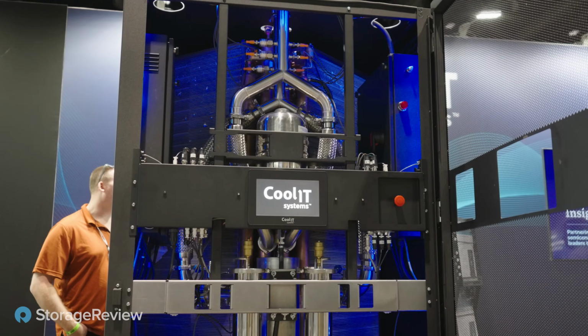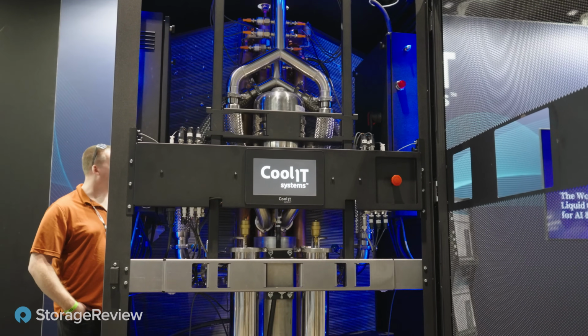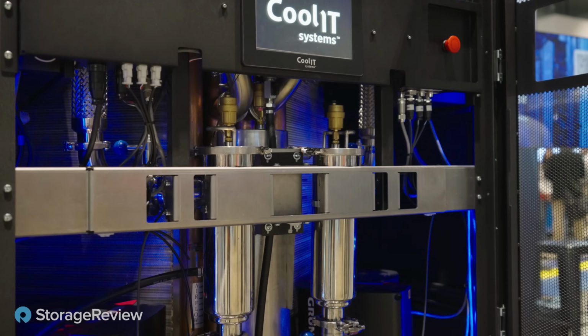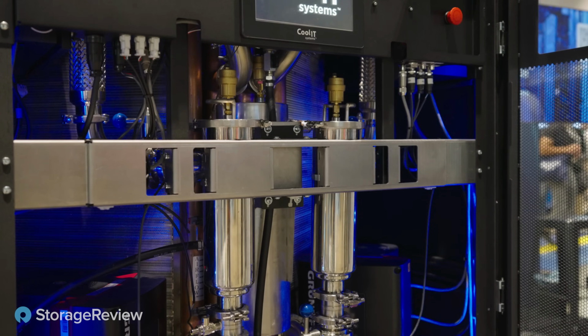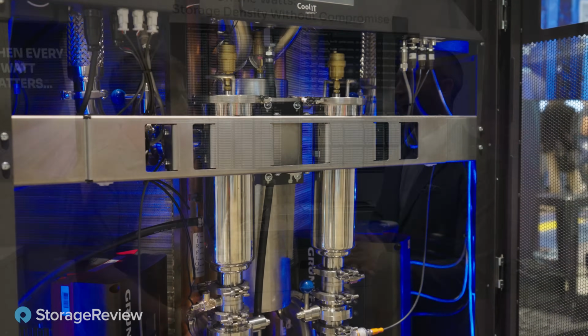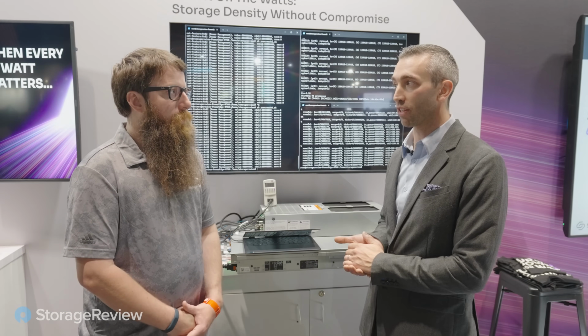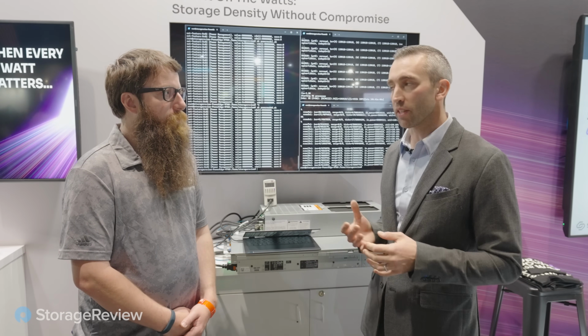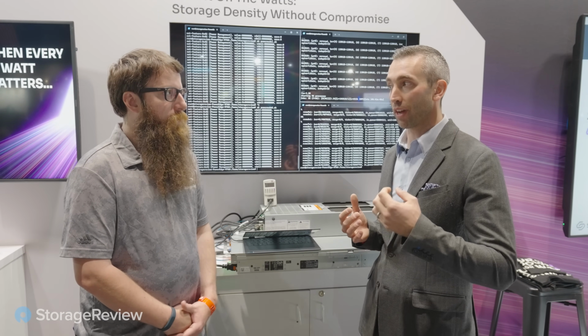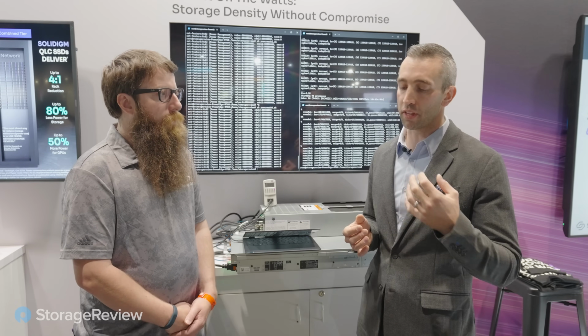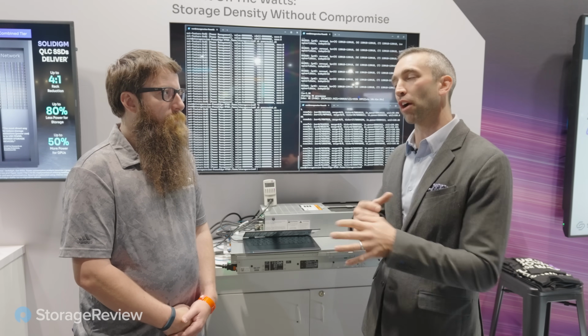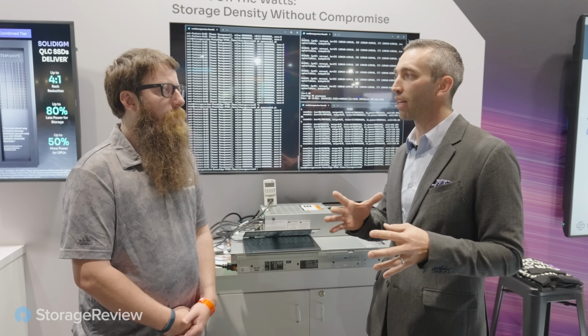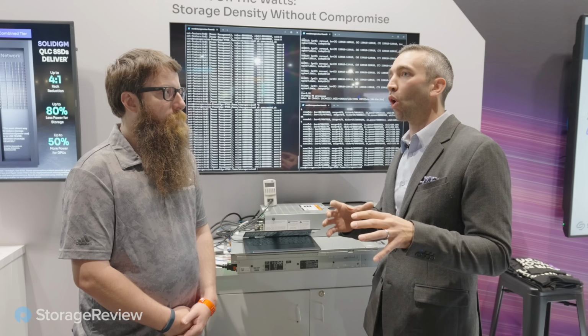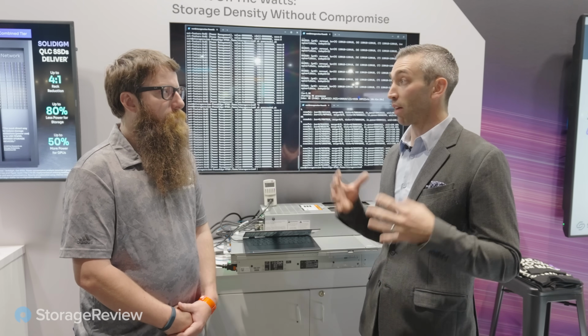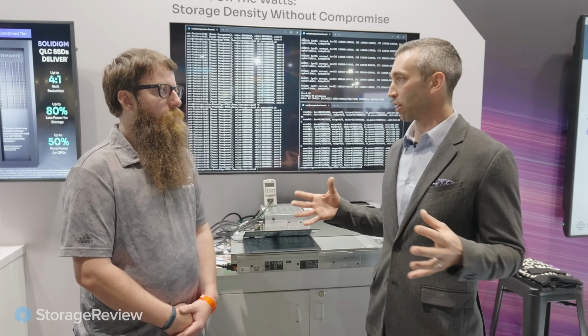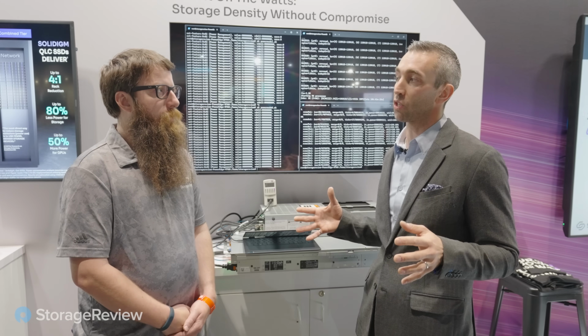For our larger form factor row-based liquid-to-air CDUs, we're aiming to support anywhere from 2 to 4 high-density racks, talking over 100 kilowatts per rack. It depends on your conditions, the heat load per rack, the air temperatures, what the chips can handle. Our team helps do all that sizing activity. Our goal with our larger row-based CDUs is to have the largest capacity in the industry and be able to support as many racks as possible.